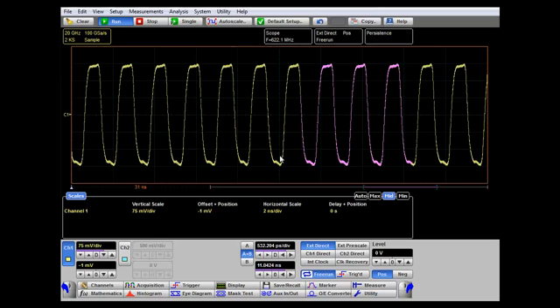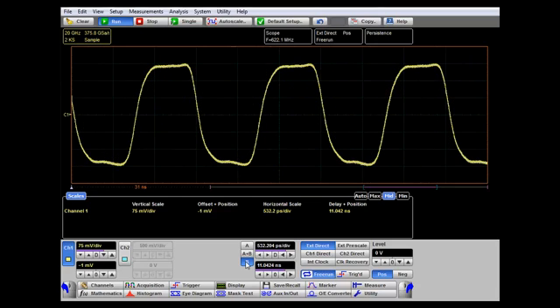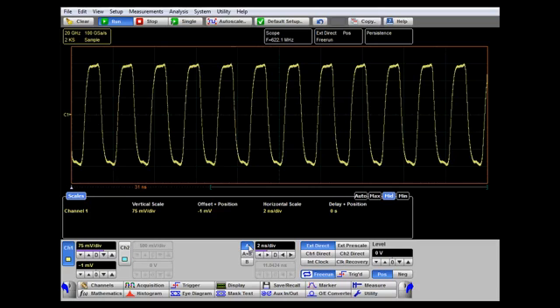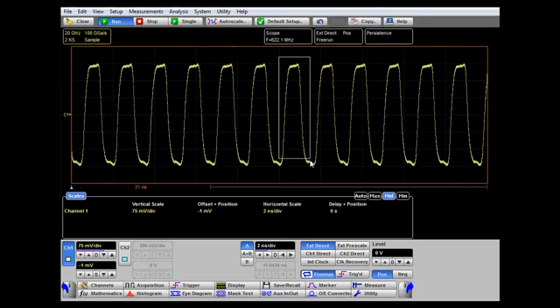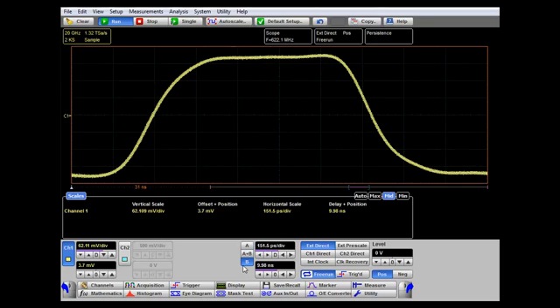Having selected an area, we can use the B time base to display those particular cycles. A second method to achieve the same result is to use the mouse — we can select any particular pulse by picking and dragging a zoom box around the waveform, then clicking inside the box, and the B time base will display that particular part of the waveform.